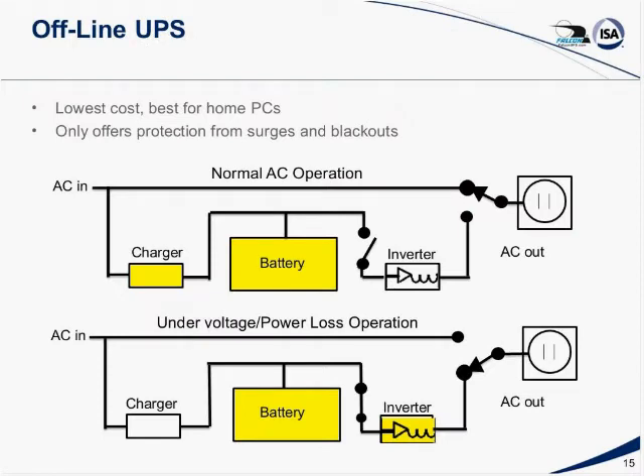Now, an offline UPS, the so-called switched UPS, is the lowest cost, and it is probably quite good for a home PC when all you need is power to do an orderly shutdown. It only offers protection from some surges, not all transients, just some surges, and from blackouts. Brownouts it protects against for a while, but in a brownout you'll keep switching in and out of the inverter and lowering the battery charge, so when you have a blackout, you do not have the capacity you think you have. Looking at the top of the slide, in normal operation, you come in from the AC mains all the way to the AC out. You're just operating on the utility power.